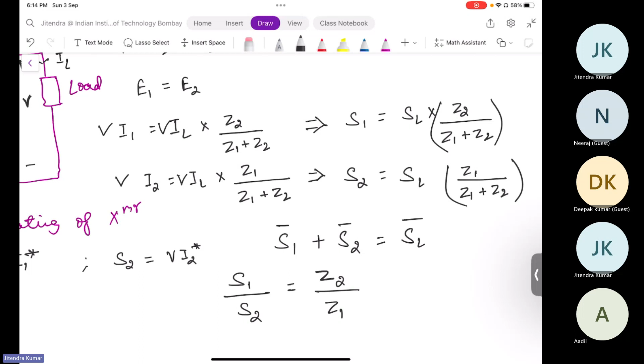Now what is the ratio of S1 by S2? Can you tell me what is the ratio of S1 by S2? Z2 by Z1. Great, Z2 by Z1. So basically, the kVA rating of each transformer is inversely proportional to its leakage impedance.